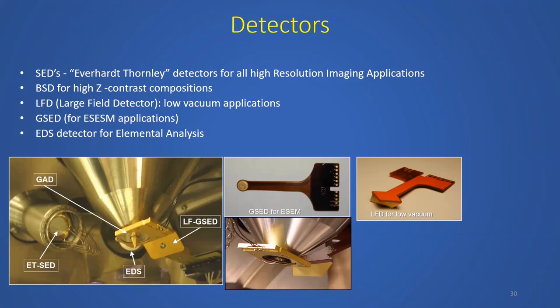So you have, as you can see here, backscattered electron detectors. These are for collecting the backscattered signals. You have large field detector, there are different names, large field detector, gaseous secondary electron detector. EDS detector is basically for X-ray signals. If you want to do elemental analysis, this is for energy dispersive spectroscopy. So you have a special spectrometer for collecting the signals and for performing elemental analysis. Okay, so these are the different detectors.